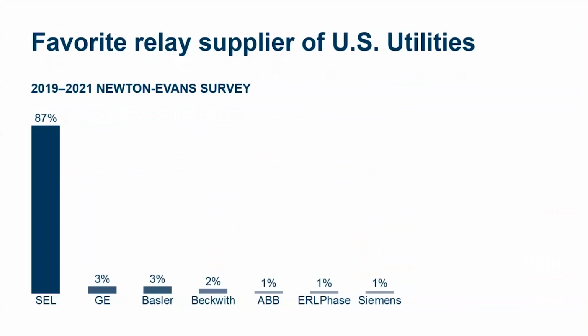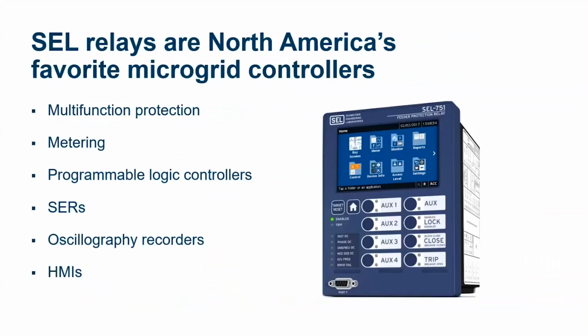And as such, we are the single most popular choice for multifunction programmable relays put at the point of common coupling. They are used and programmed by our customers to provide automatic islanding, automatic restoration, load shedding, synchronization, and so many more microgrid functions that are required to provide a reliable power system to your microgrid customers.